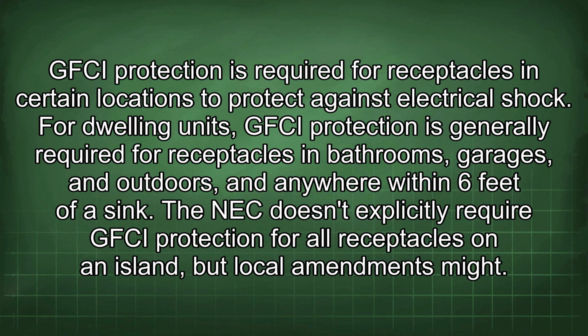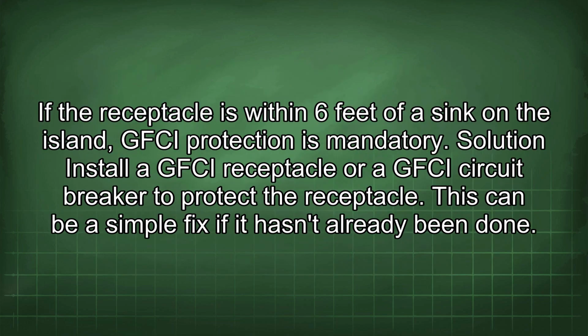For dwelling units, GFCI protection is generally required for receptacles in bathrooms, garages, and outdoors, and anywhere within 6 feet of a sink. The NEC doesn't explicitly require GFCI protection for all receptacles on an island, but local amendments might. If the receptacle is within 6 feet of a sink on the island, GFCI protection is mandatory. Solution: install a GFCI receptacle or a GFCI circuit breaker to protect the receptacle. This can be a simple fix if it hasn't already been done.